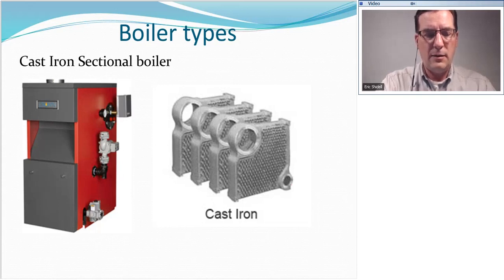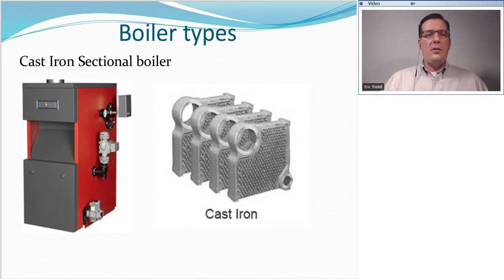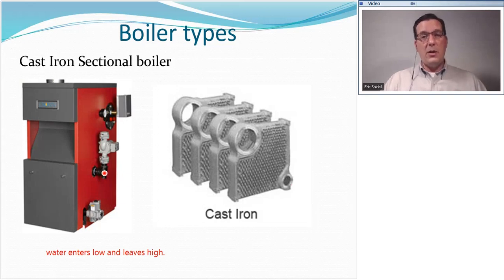So for example, here we have one connection down here, and the supply connection is on the top, I think, of this boiler, or it's around the side near the top. This would be the lower, this would be water entering. The other would be water leaving. This is an important part of identifying which direction the water moves in your system. So on cast iron boilers, water is always in on the bottom, leaving on the top.